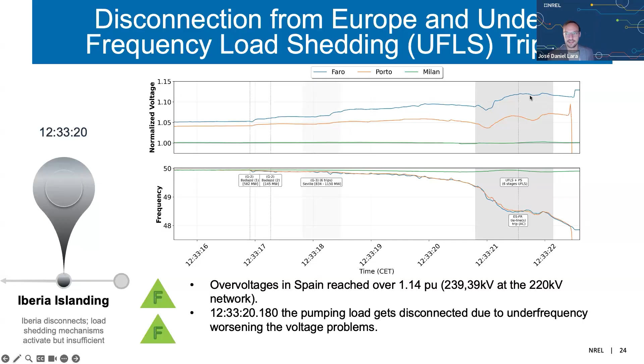And again, in this last bit of time, here's a little bit of where we left off in the last trip. And you can see here the voltages continue to creep up. They come down a little bit and then continue to go really high. And this is due to the trip of the hydro pump storage. Again, the hydro was consuming active power, but it was injecting reactive power. And due to the under frequency load shedding, you lose also that capacity to absorb reactive power in the system. And by that time, all of the 6 stages of the frequency load shedding happen. You lose the pump hydro, the voltages get completely out of reasonable operating values, and the system blacks out.